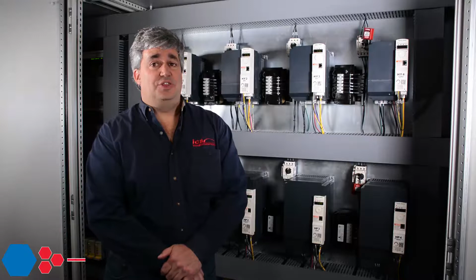For a blower, if I want to run it at 3 speeds with relay technology, I need to wire 3 relays into a VFD to control that speed. With Ethernet, it's still just one cable going to each drive, and we can tell the drive what RPM to run. We get bidirectional feedback, so we know it's running at that speed, we know the amperage, we know what's going on with that whole little control system.